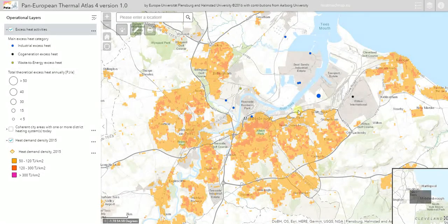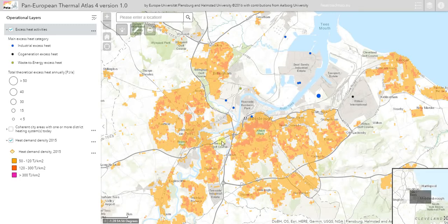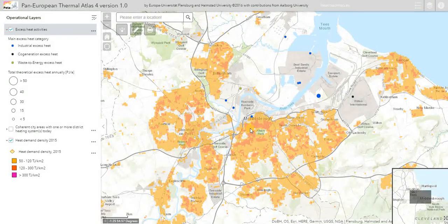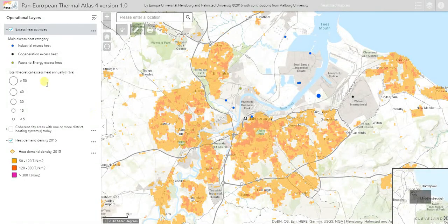Adding all of these together, the total excess heat in the Middlesbrough area is about 35 petajoules per year. And from the heat density map I can see there are ideal locations to start developing district heating in the city, because the dark red and orange areas show heat demands much higher than would typically be required to develop district heating.